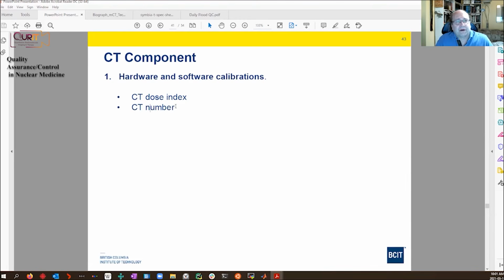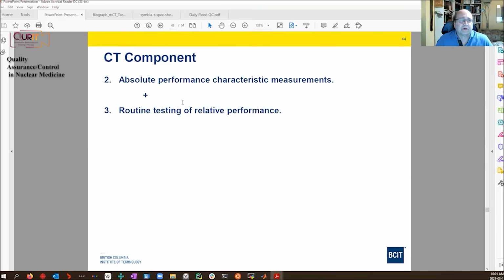CT number, if you haven't done CT, is a value relative to water. So the CT number of water should be 0 by definition, and you want to test that you're getting an accurate CT number out. A value that's very important for measuring patient dose in a scan is the CT dose index, which I'll describe in a minute.